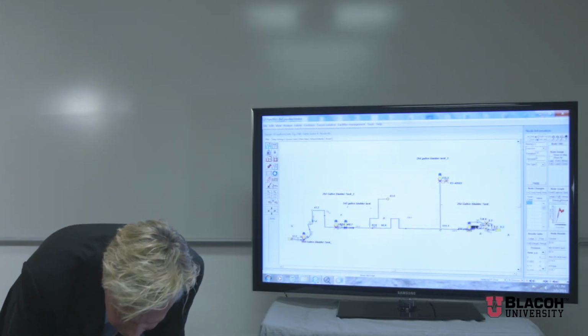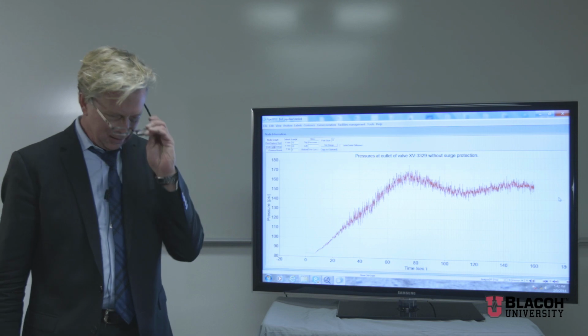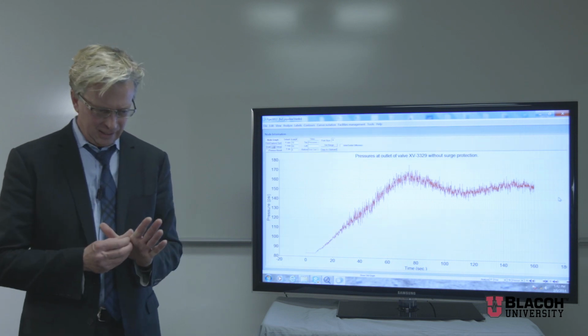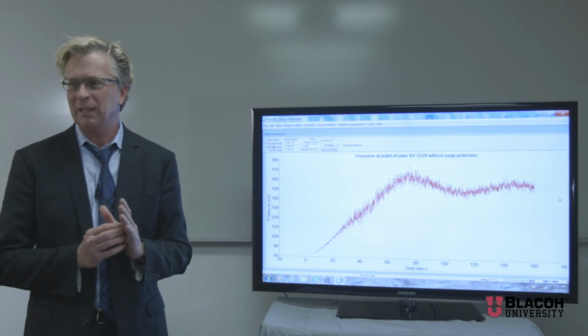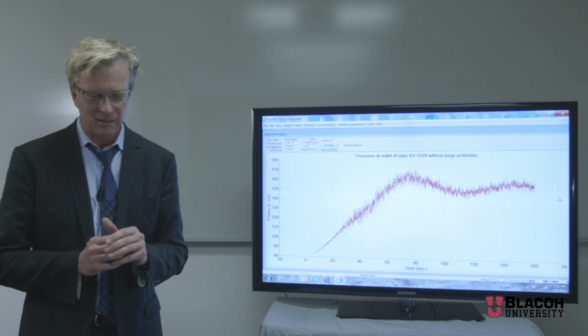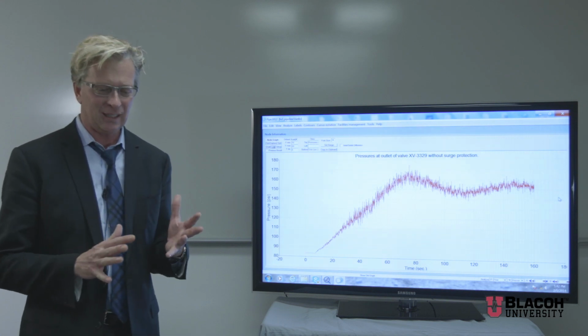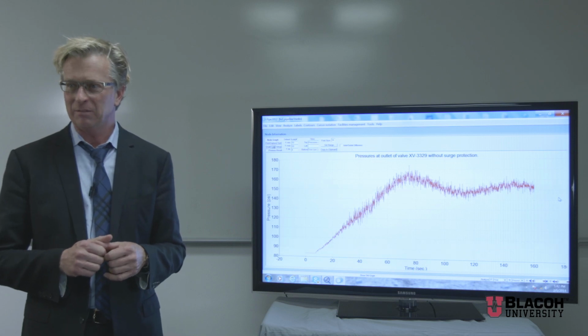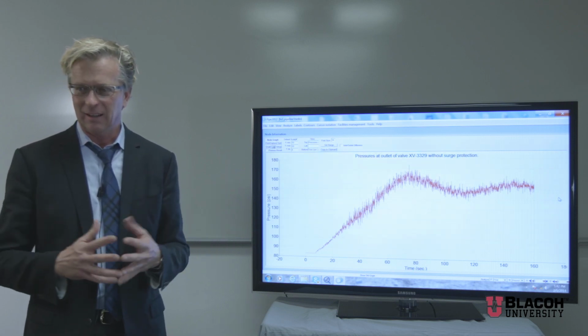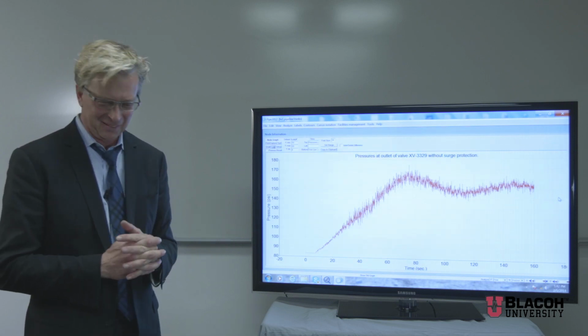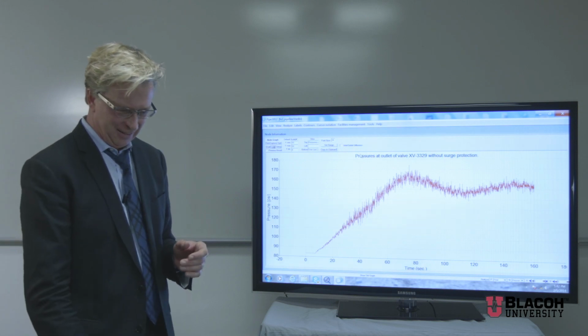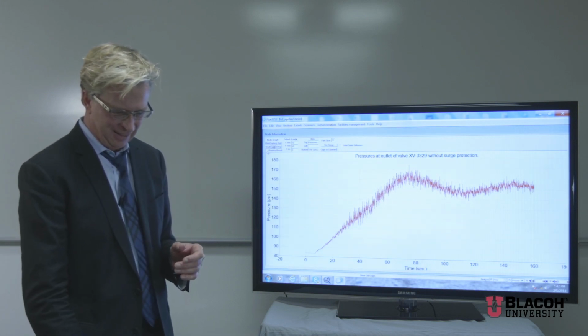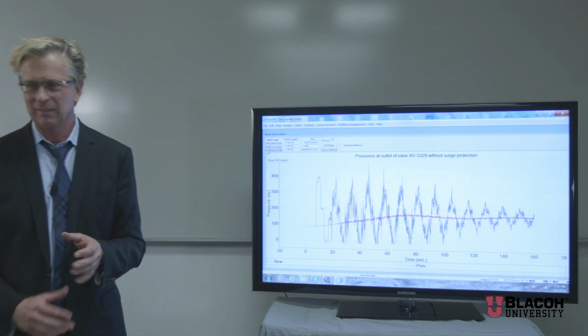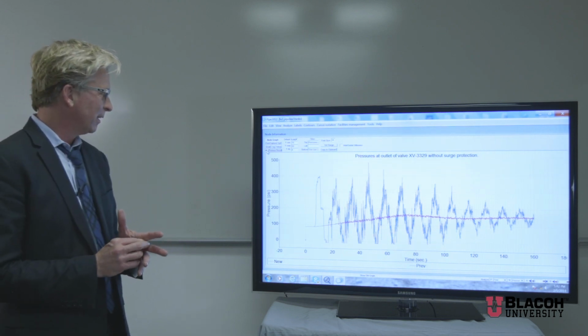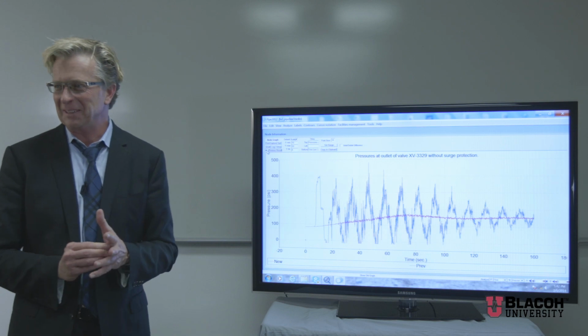All right, so here's my safety relief valve. And the key to this design was that I didn't get to 170 PSI, okay? If I could keep it below 170 PSI, that relief valve's not going to go off, which means I'm not going to have to deal with this problem.